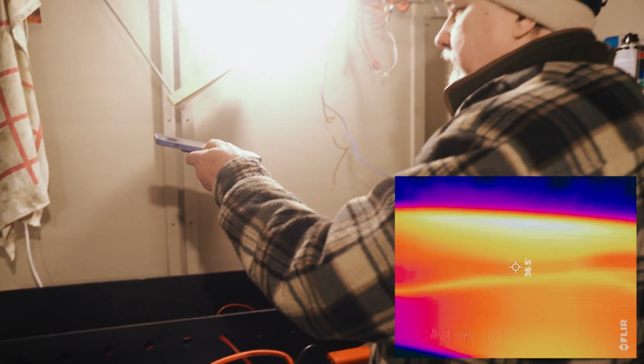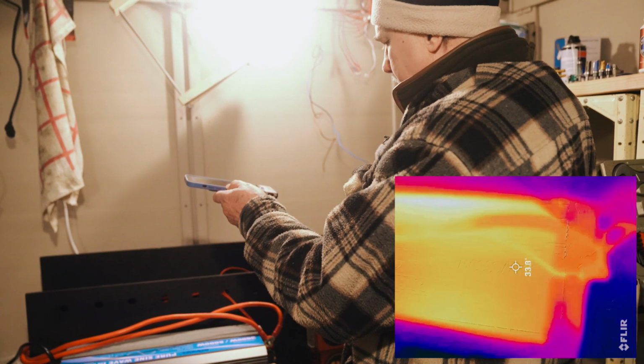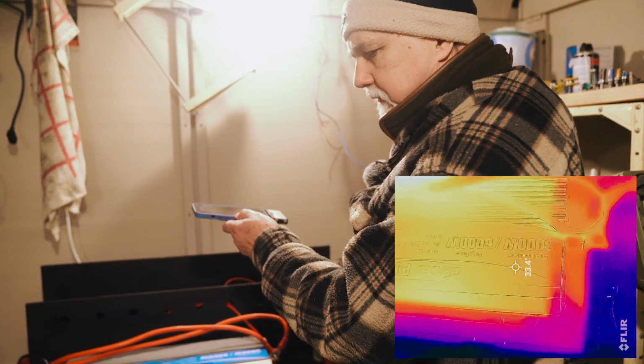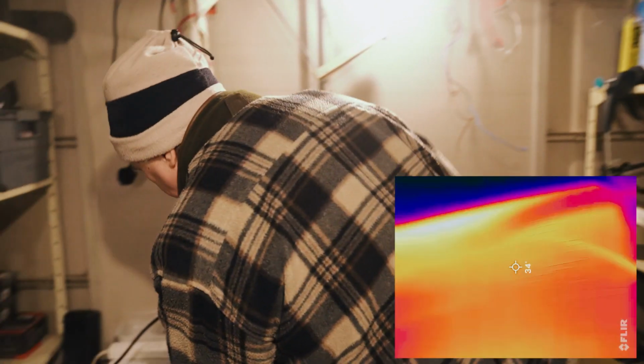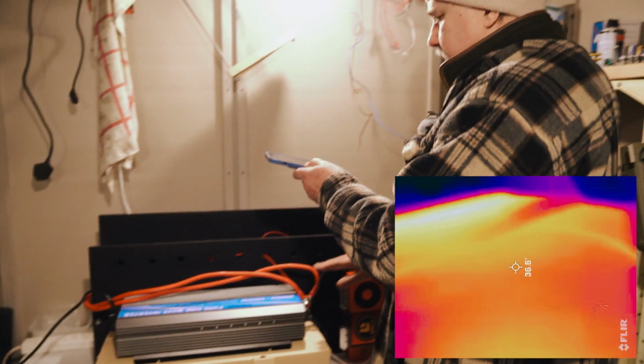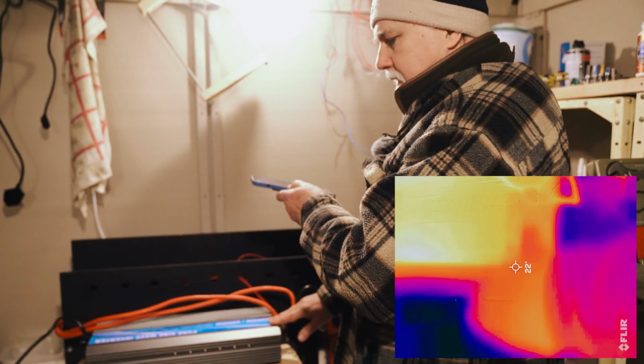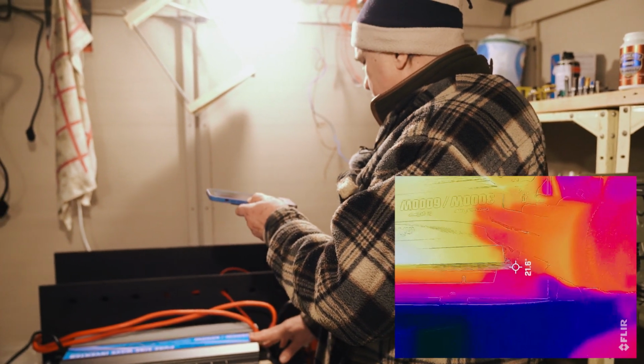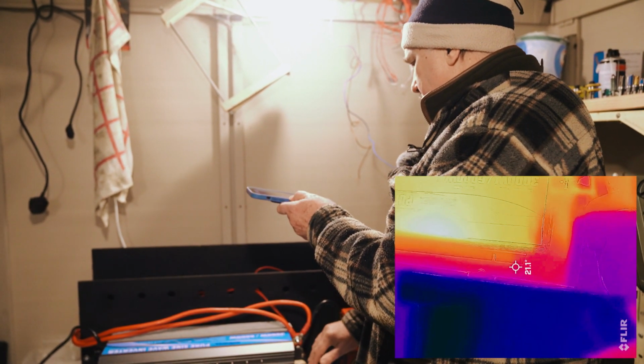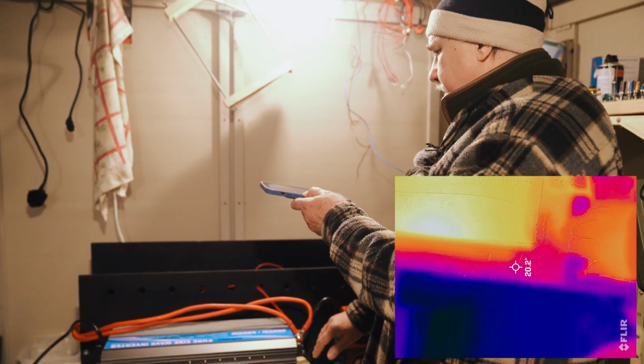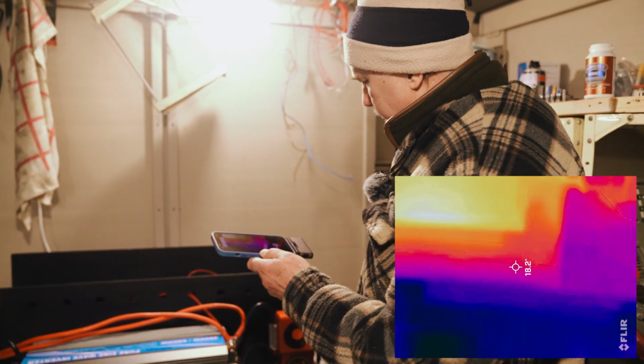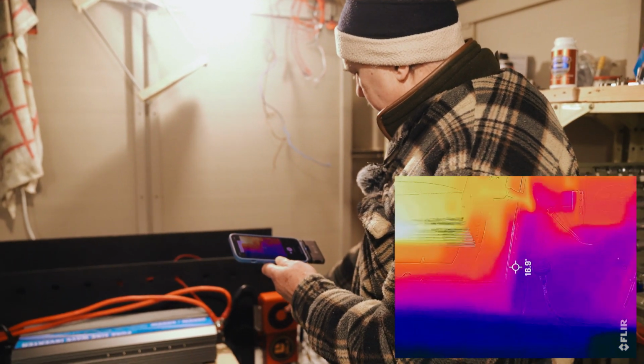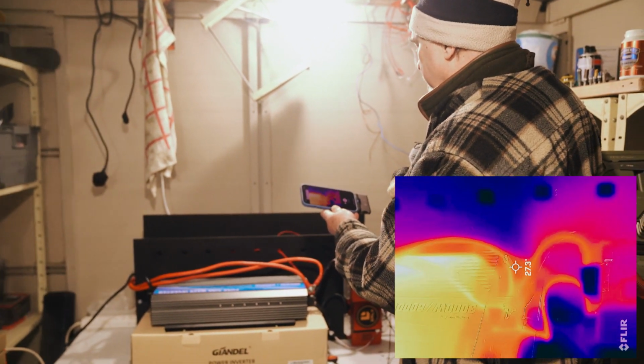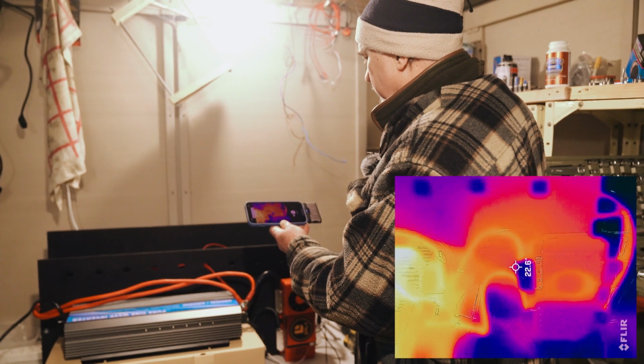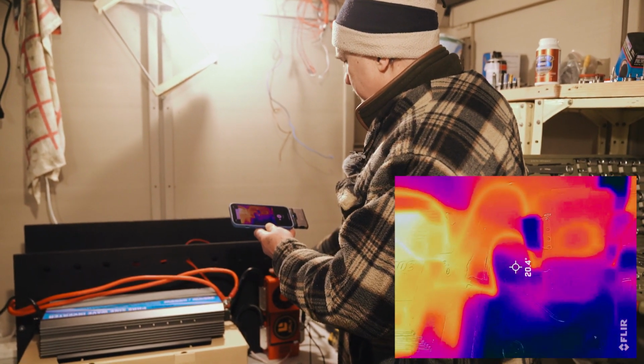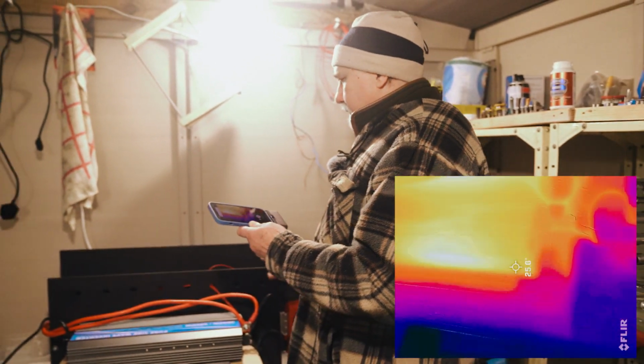So far, looking at everything, I am completely satisfied that we do not have a problem drawing 2.8 kilowatts. The inverter is still drawing 2.7 kilowatts. The induction hob is running 2.8 supposedly, and there's warm air coming out of the inverter, not really hot. The BMS fan hasn't even turned on. Looking at it with the FLIR camera, it's really not that warm, in fact it's fine, absolutely fine, not much heat coming out of here. So this rig is operating really well.